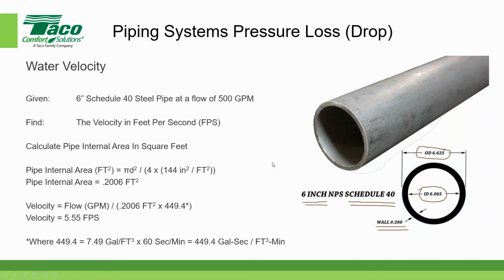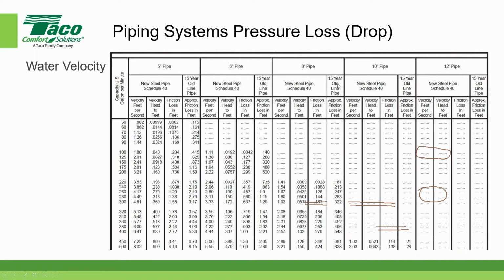All right. And if we look that value up on a table, let me erase some stuff over here on the right. There we go. There are lots of these published tables out there. This particular one I downloaded from the internet, and it shows the relationship between the pipe size over here. Let's highlight a few items. In our case, we had 6-inch pipe, and we're running at a flow of 500 gallons per minute. The velocity is this column over here. Again, this is Schedule 40 steel pipe.